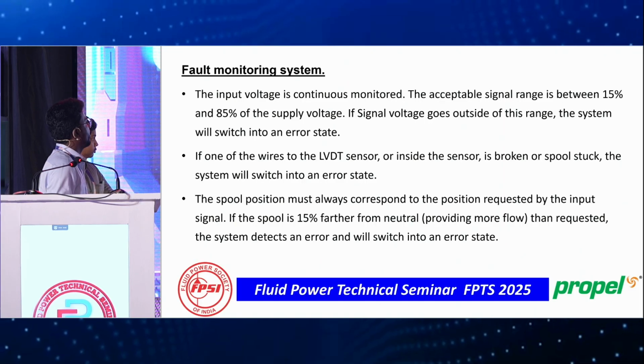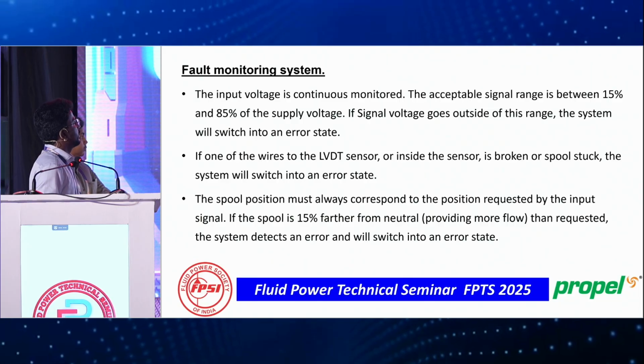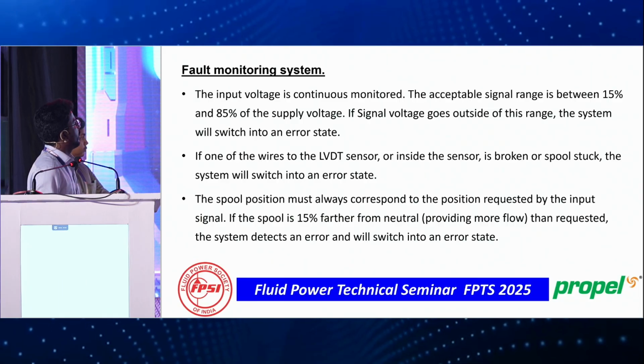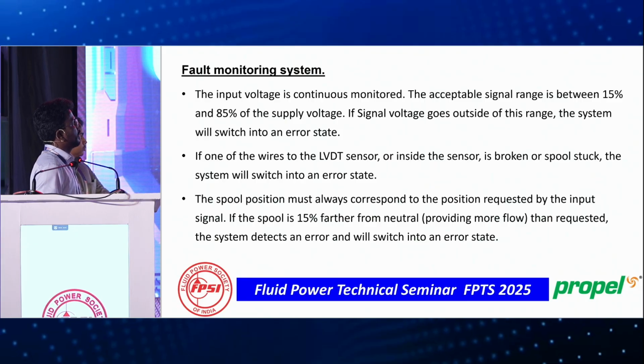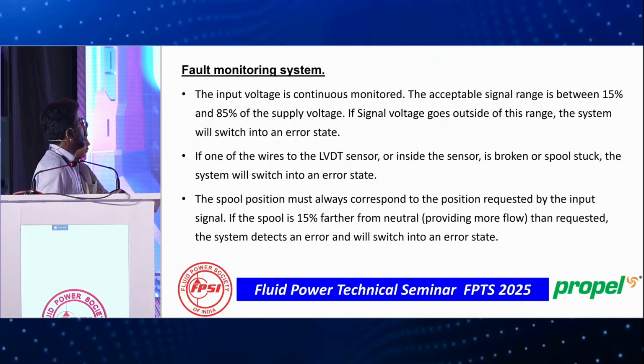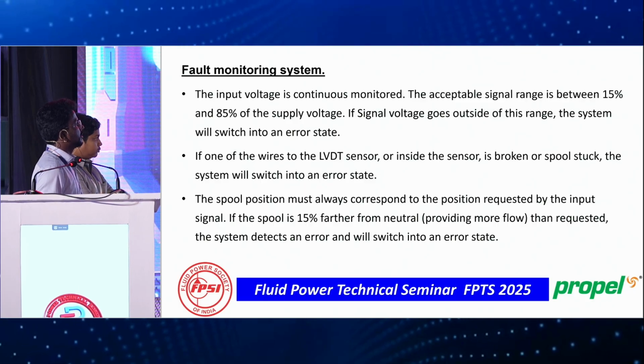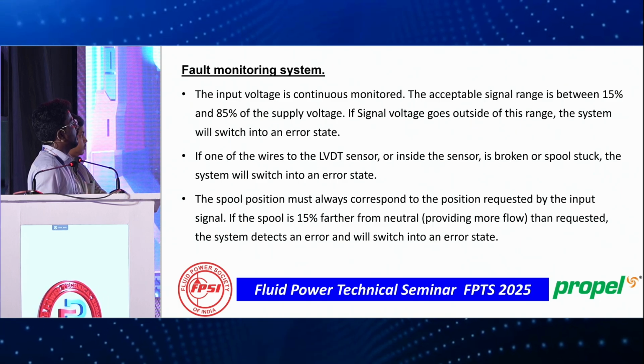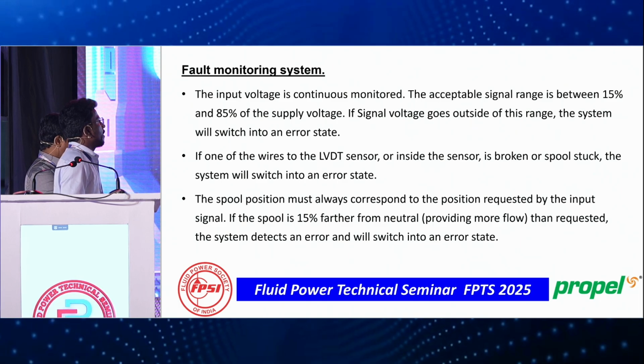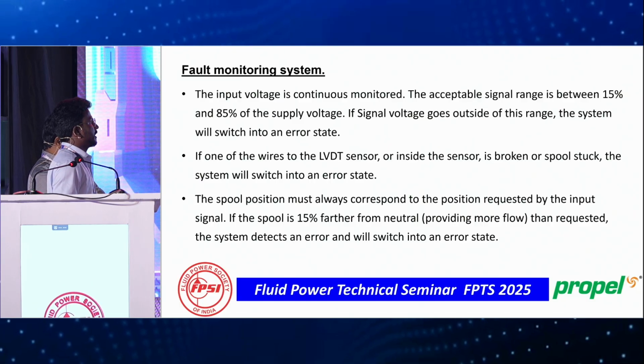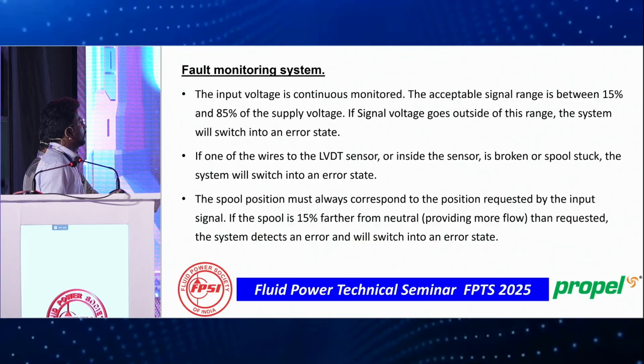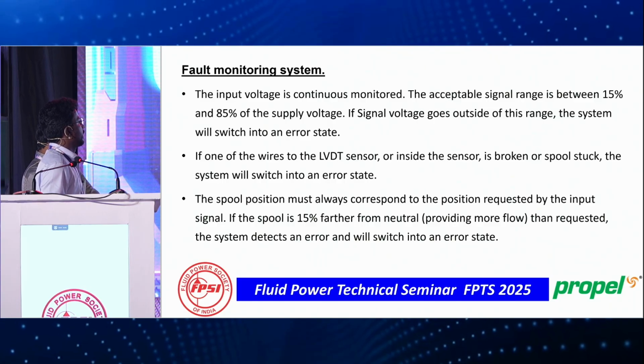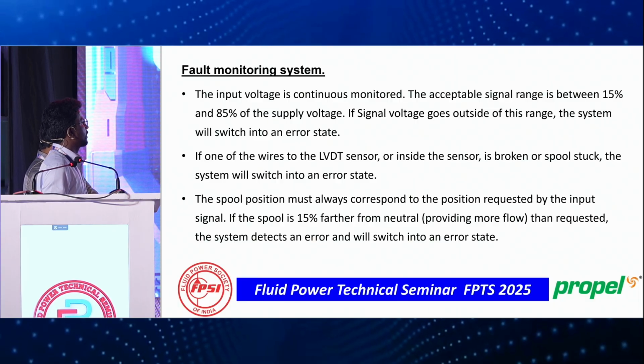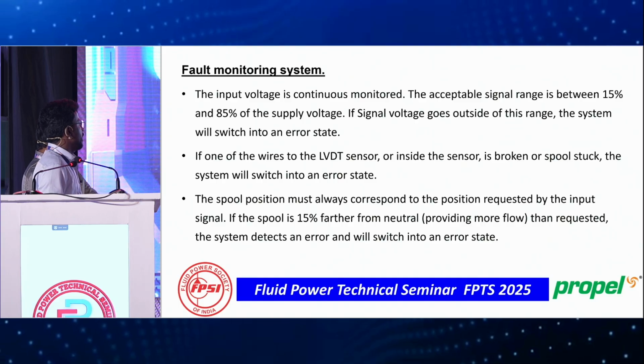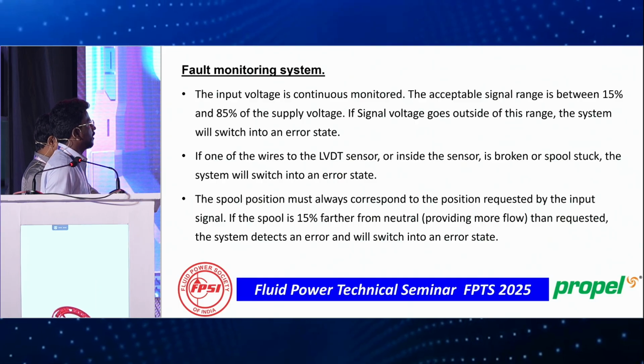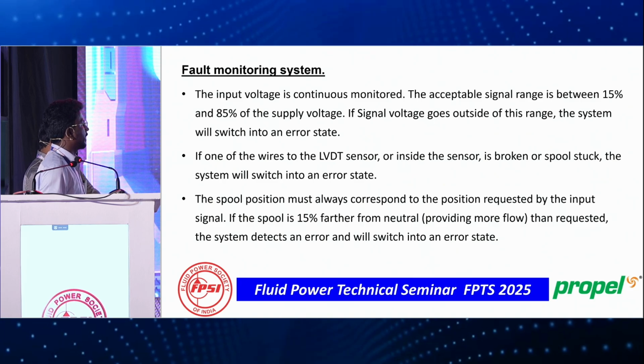This is the typical explanation of the fault monitoring system. The input voltage is continuously monitored. The acceptable signal range is between 15% and 85% of the supply voltage. If the signal voltage goes out of this range, the system switches into an error state. If one of the wires to the LVDT sensor or inside the sensor is broken, or the spool is stuck, the system switches into the error state. This is helpful when the spool is stuck, because the machine may move suddenly or may not move at all, so reviewing the error state is really helpful for crawler operations. The spool position must always correspond to the position requested by the input signal. If the spool is 15% further from the neutral position than requested, the system detects an error and switches into the error state.